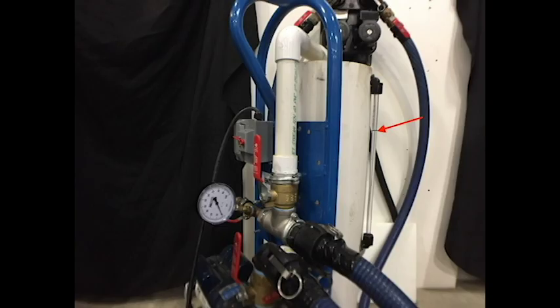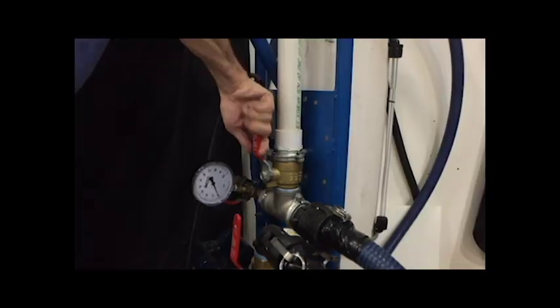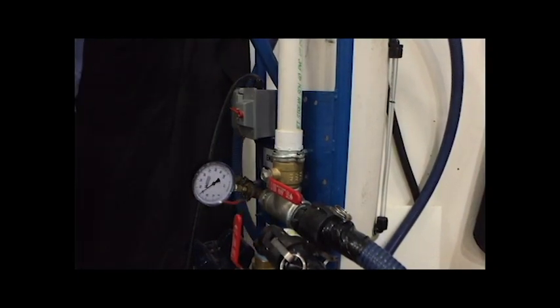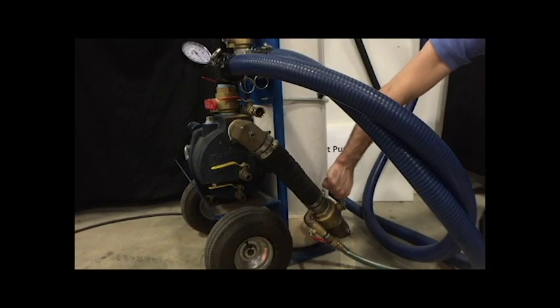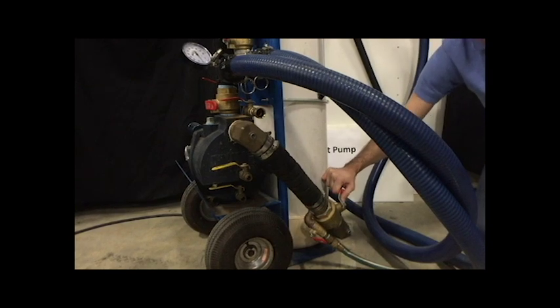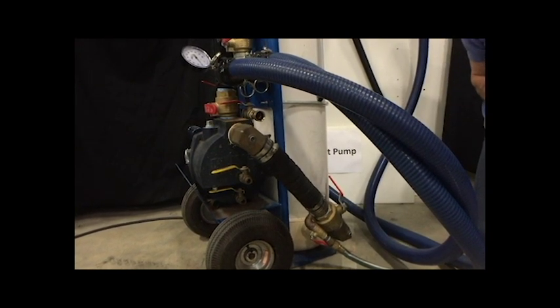The following procedure describes this process and assumes that the steps in the standard flushing purging video have already been completed. Since the power flushing procedure adds fluid to the tank from the water supply, lower the tank level to avoid overflowing before starting this procedure. With the pump running, close the inch and a half deadhead valve and close the two inch tank isolation valve. Then open the half inch fill valve.